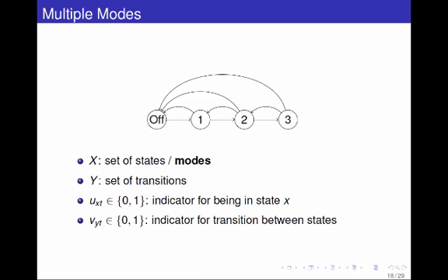The way we model this, the model you see in the literature, the model that GDF Suez uses, and the approach we use with Pacific Gas and Electric, is you have a state diagram. You can be in one of 4 states. You can be off. You can start up a single generator, but to start up a second generator for the plant, you need to have the first one started up. That's basically what these arrows are indicating. They're possible transitions. Now we want to think of how we can model this as a math program.